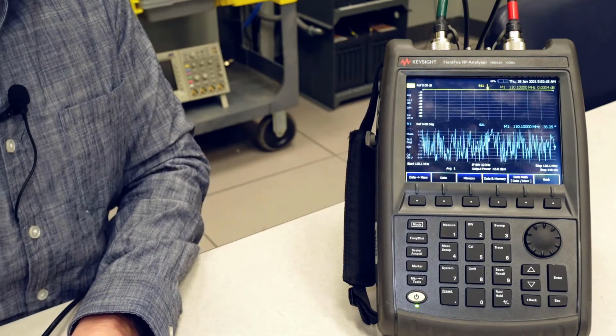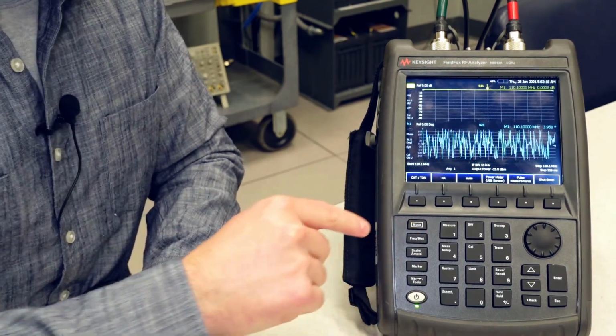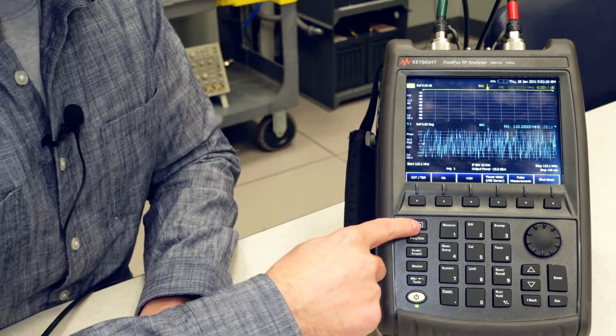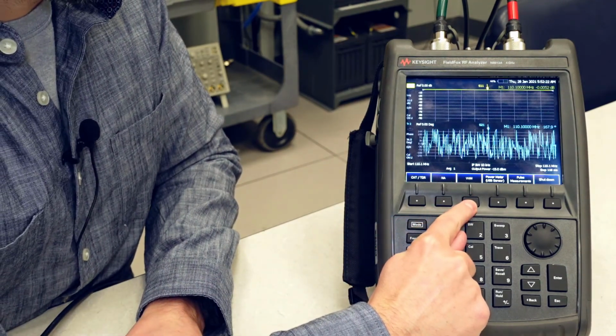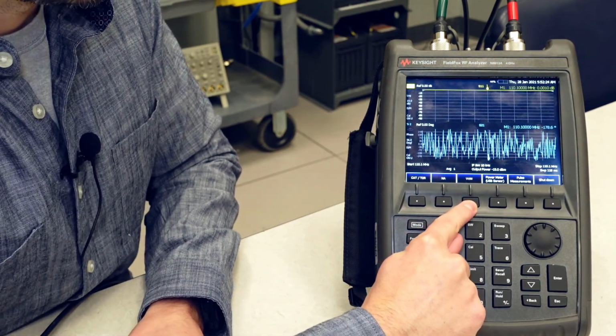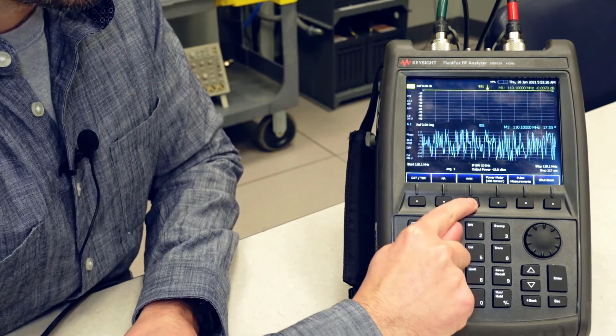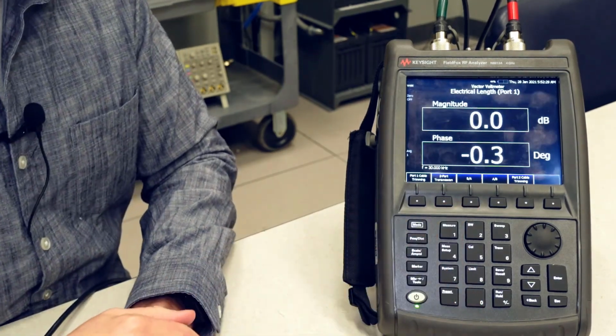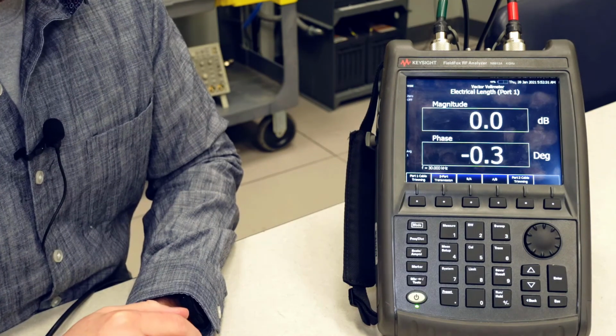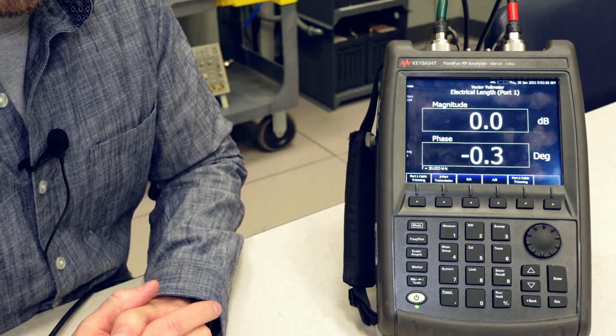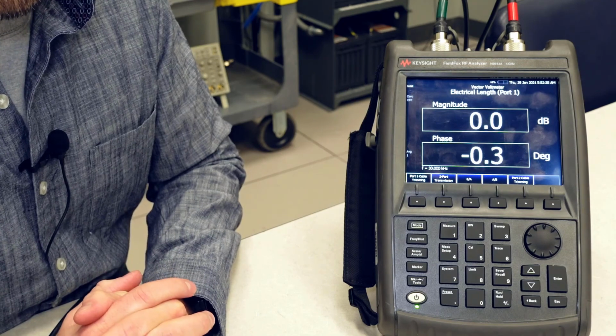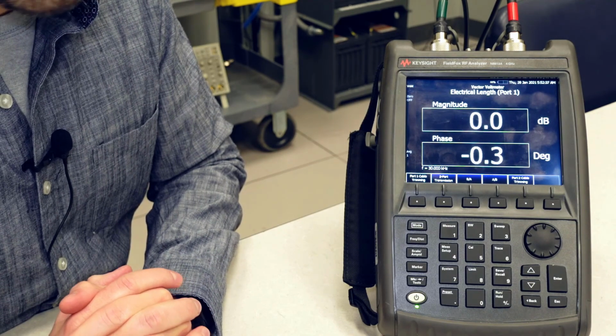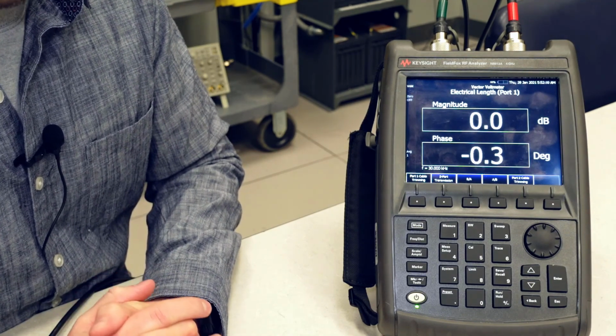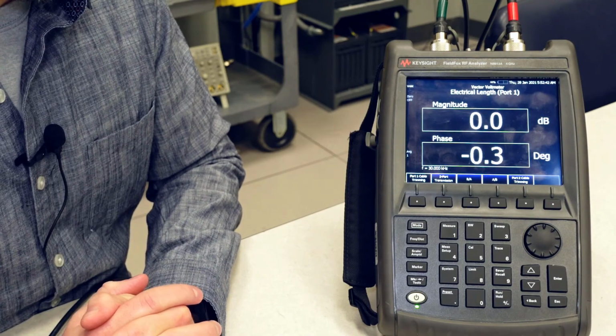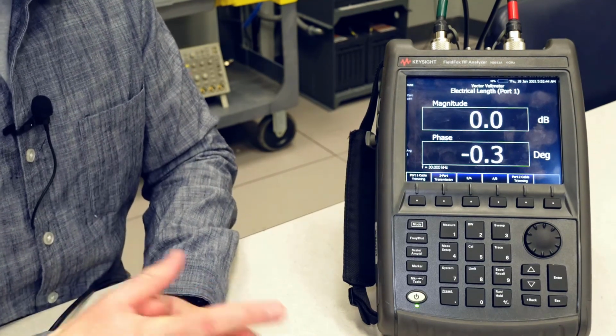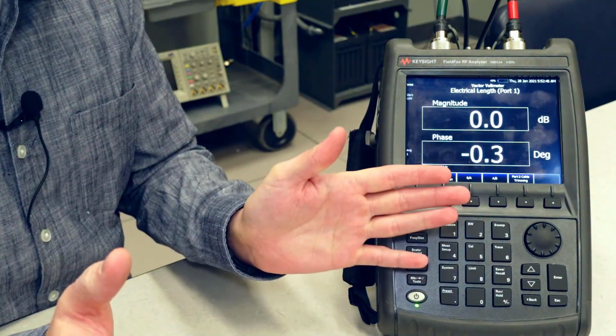Let's look at the Vector Voltmeter Mode. When you select mode, you should see VVM as an option. This is option 308, so you'll have to have that installed if you want to access this feature. Now the great thing about the Vector Voltmeter Mode is it's very easy to use, but it's only designed to be used at specific frequencies. So unlike the network analyzer, you can't use this mode to sweep a range of frequencies.